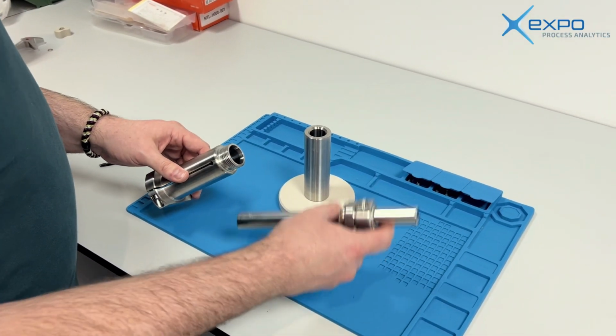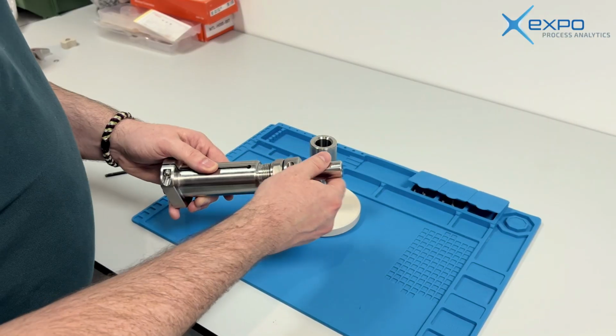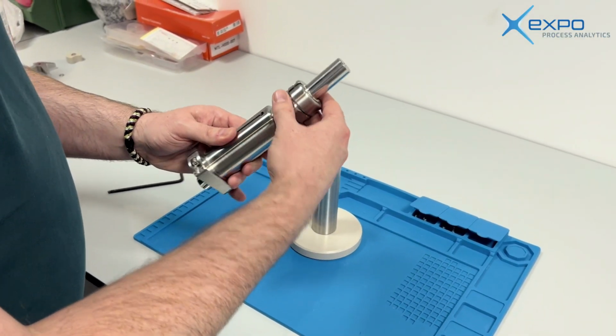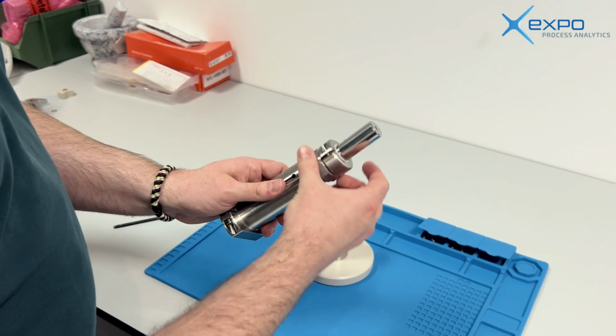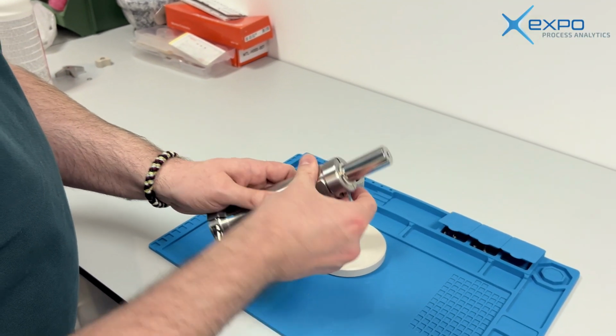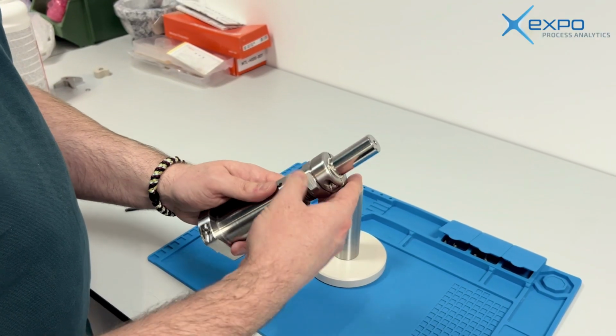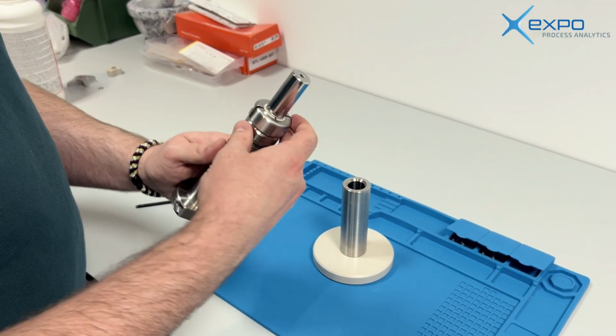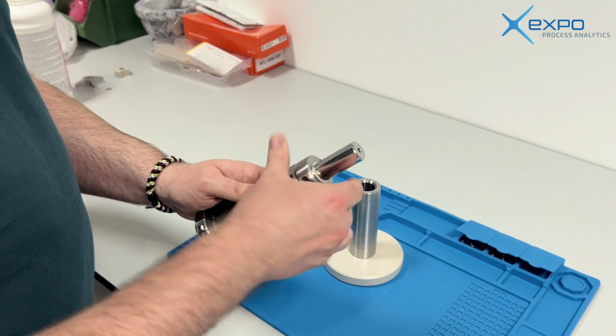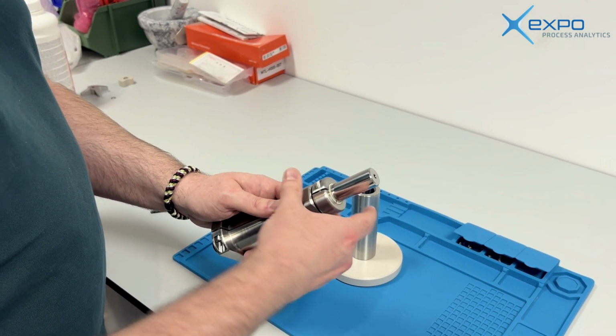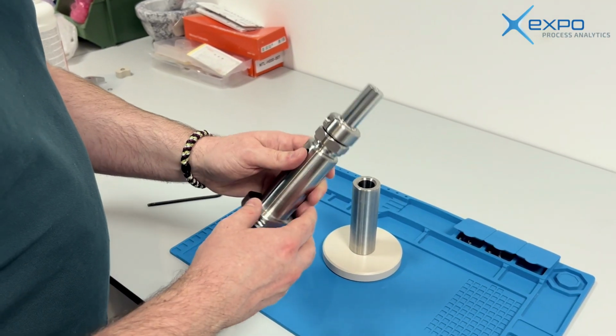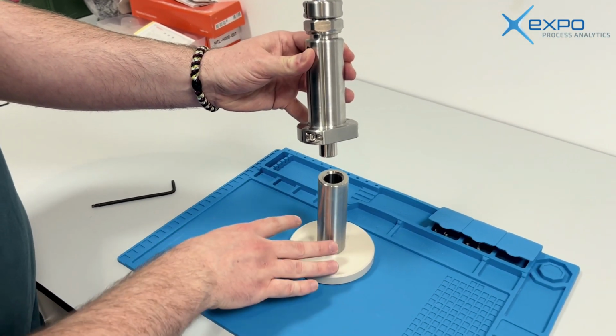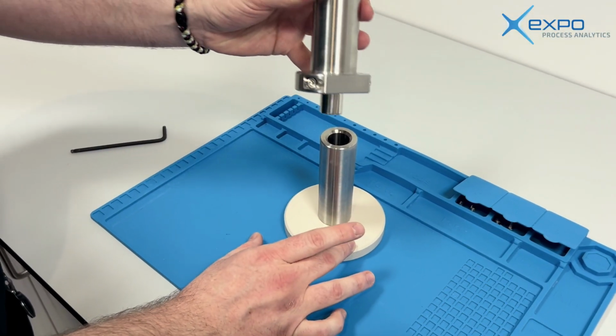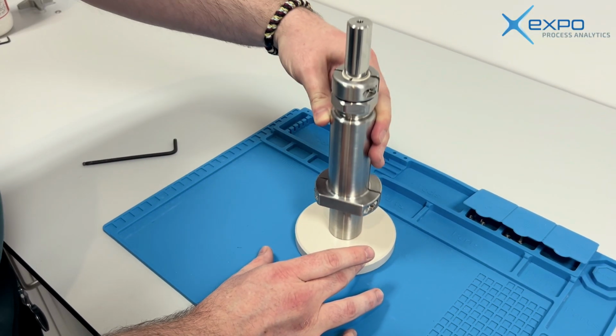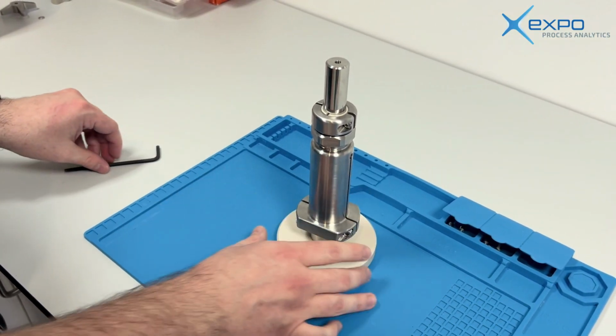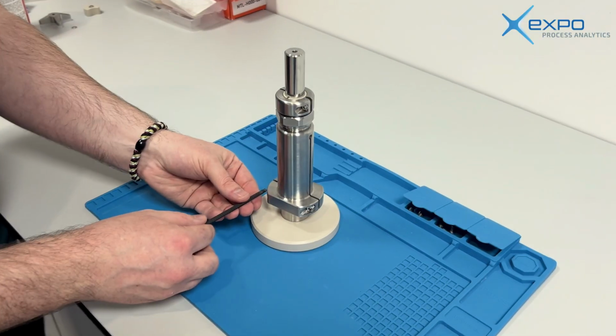So initially, what you can do is feed the dummy probe through the sliding component and thread it on. So you'll thread it on all the way, and you just have to make sure that when you're tightening it, you torque it to the same value that it was torqued to on the back of the device. So I'm just going to hand tighten it here, but this would need to be torqued to the same value. At which point you're going to slide this down over the fixed component until the dummy probe bottoms out on the polymer base.